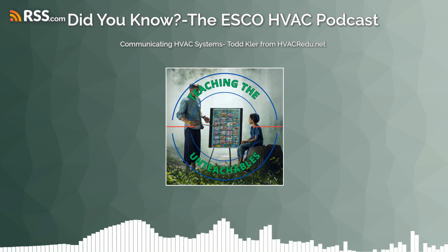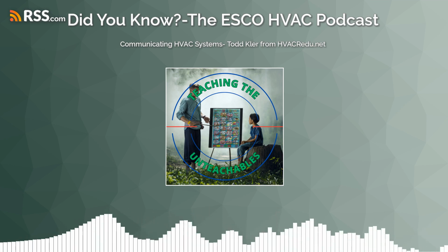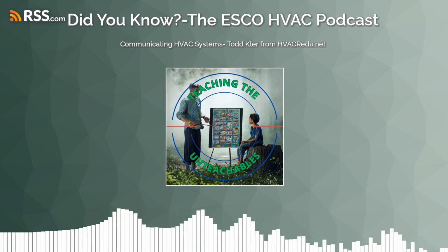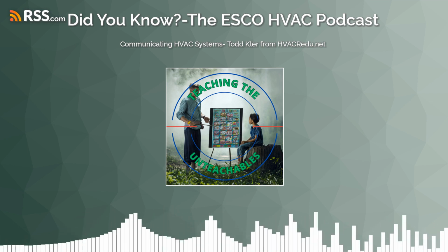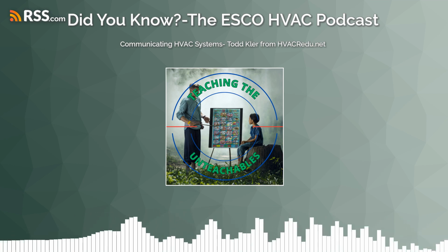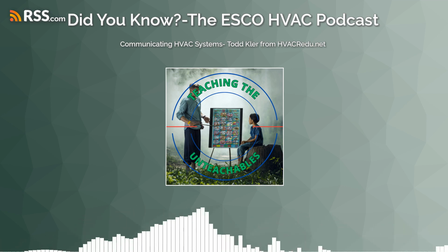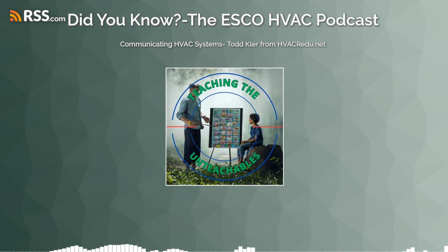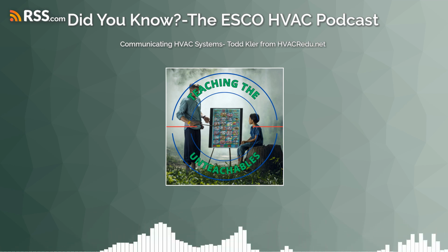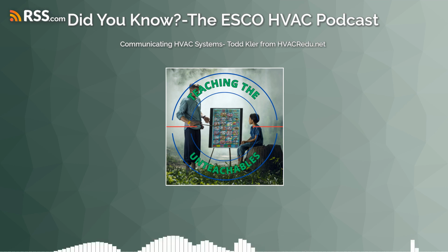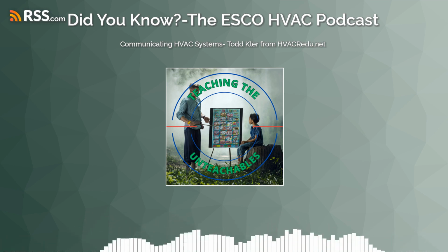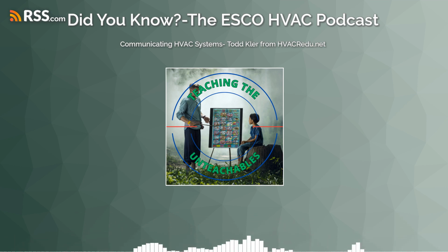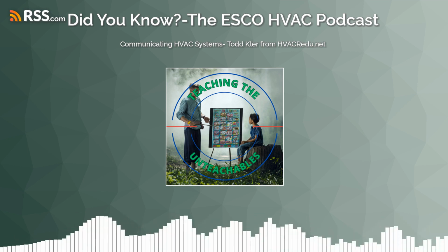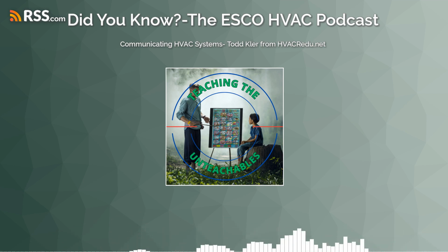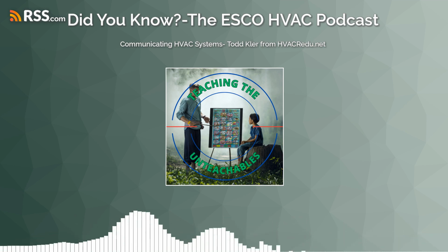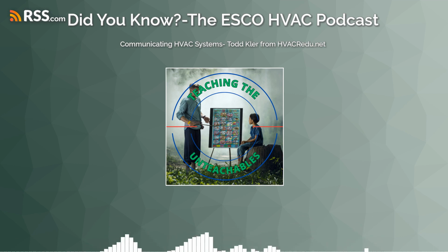Now, if I were just a guessing guy, Todd, and if I didn't go into the next slide we're getting ready to look at, I might look at that and go, I got 2 wires going to my outdoor unit. I wonder what's on those 2 wires. Well, if it's the outdoor unit and it's communicating, it probably has its own transformer. Right. We usually don't have common hooked up, rarely ever, unless we have a problem like you described. Exactly. We're not going to have R hooked up. So the only other 2 wires there, in this case, green and yellow. One's got to be a positive DC and one's got to be a negative DC.